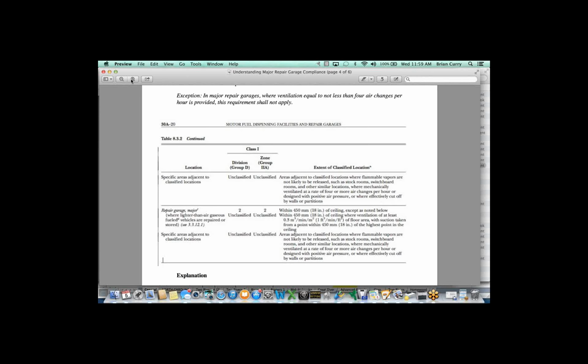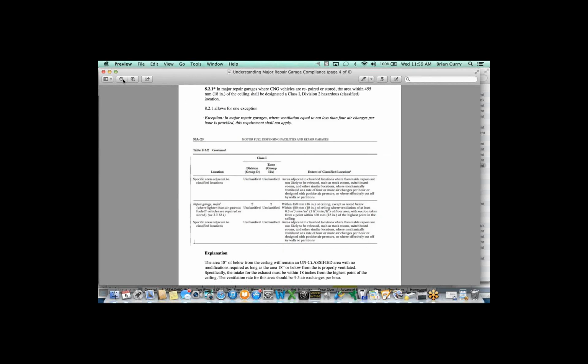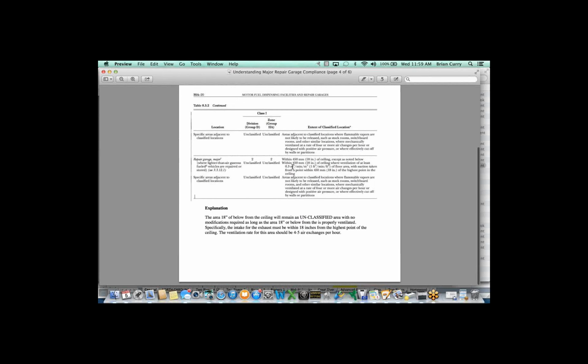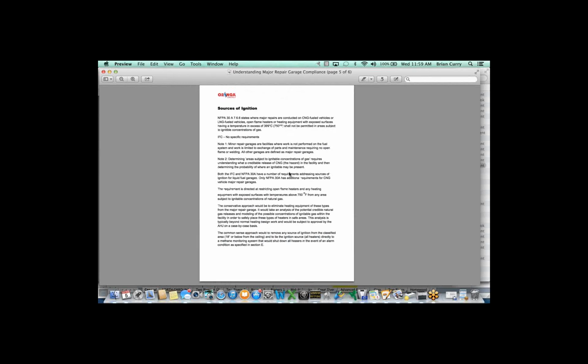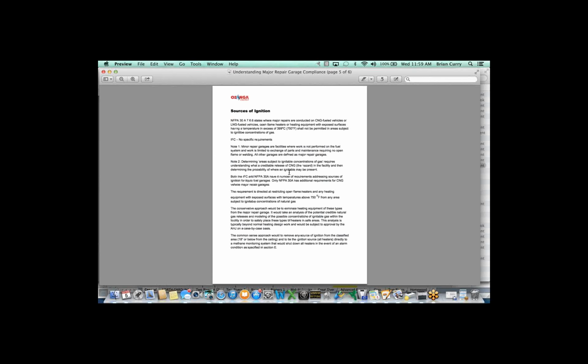Moving down the line, getting into some of the best practices I've seen, I'm going to touch upon the heaters. This is another question we get asked a lot too. What do you do with the heaters? And as Steve had said, the way the code is written, basically you can't install an open flame heater or a heater with a heat exchanger that exceeds 750 degrees in any area subject to ignitable concentration of natural gas. Yeah, that's a tough one.